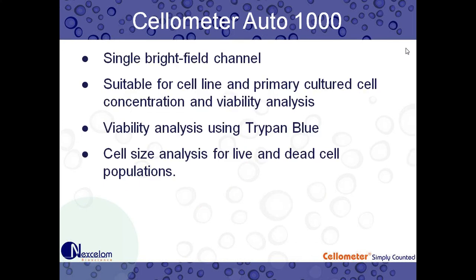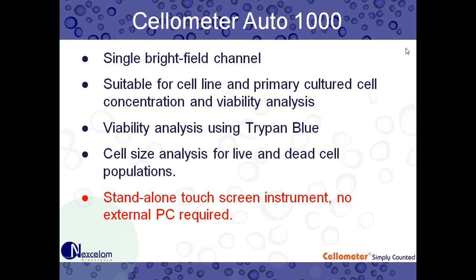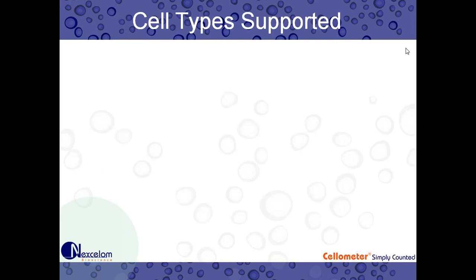So our Auto 1000, the same single bright field channel suitable for cell line and primary cultured cell concentration viability analysis. The viability analysis is done using Trypan Blue. And then the cell size analysis is also performed. And this is a standalone touchscreen instrument. There's no external computer required. So the computer's built in. It's standalone and it takes up very small bench top space.